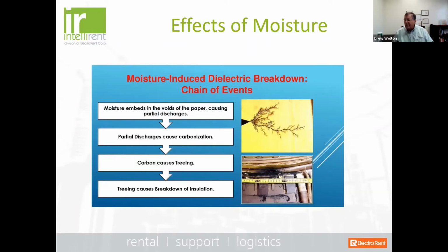So if we look deep into this, the moisture-induced dielectric breakdown, there's a kind of chain of events. It embeds in the voids of the paper, causing the partial discharge. That will cause some carbonization, and that will cause a treeing effect that you can see in this picture right here. And then eventual treeing causes the breakdown of the insulation, and you can kind of get an indication right here.